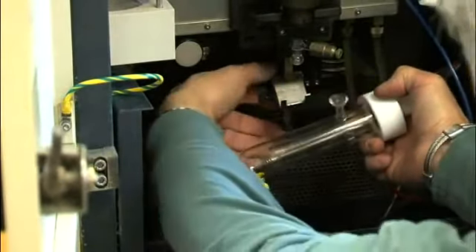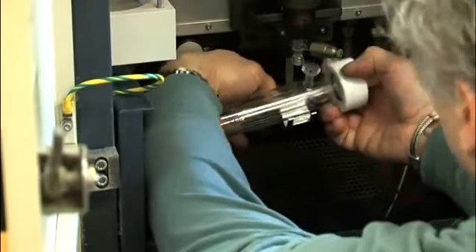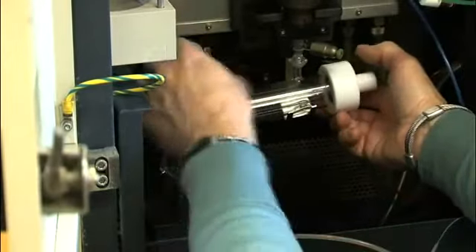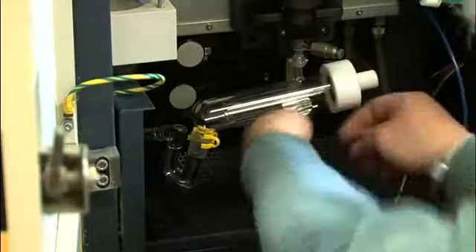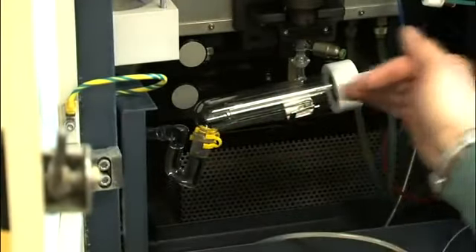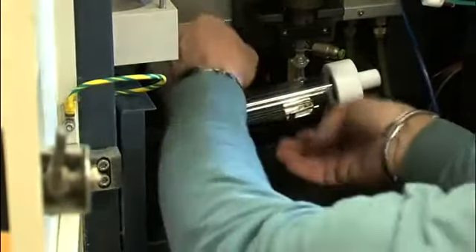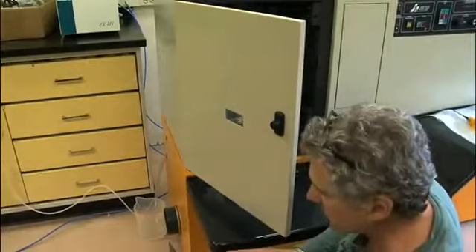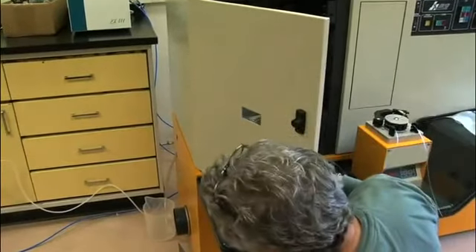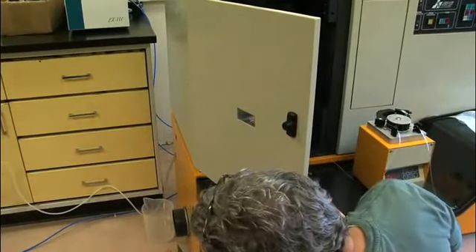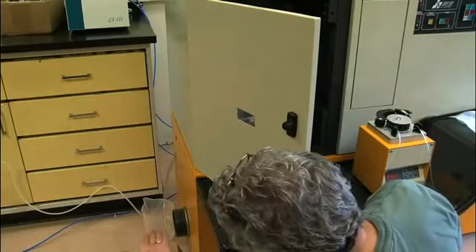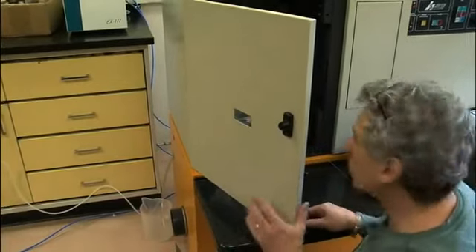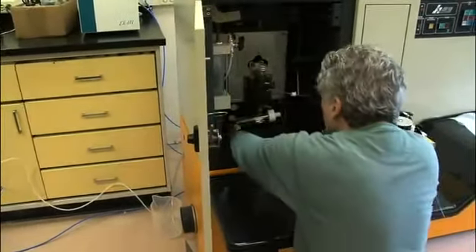You need the back pressure on the spray chamber so your sample will go up. If there's no water in here, your sample is just going to go right out the bucket and you won't see anything. So we push this down, put the spray chamber in, and it should have an angle to it so gravity feeds out. And the same with the drain tube. You don't want it sagging to create another dip, so you have a second back pressure, because that'll cause all kinds of problems. If that bucket fills up past the tube, it's going to cause another back pressure. You don't want that. All right, so put the clamp on.